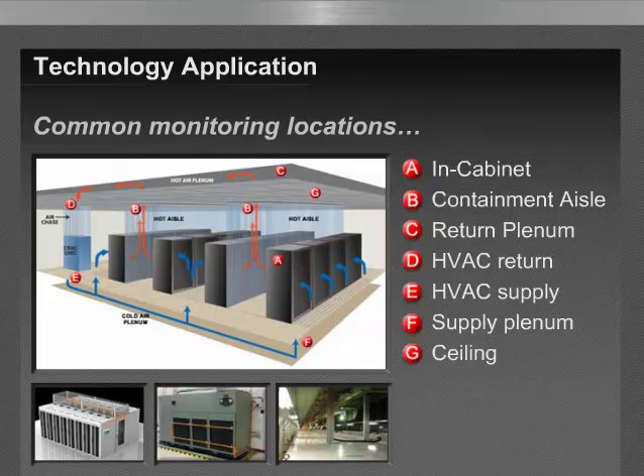And the point we're making here is that the further you get from the source, the greater the compromise. So if we look at the cabinets, for instance, sampling within the cabinets would be ideal. And if you didn't decide to sample within the cabinets, the first place that smoke would migrate to under this hot aisle configuration would be to the return, the ceiling return plenum. And so placement of sampling within the hot aisle at that point presents an opportunity to detect at that location. Now you're making a little bit of a compromise there because you're not able to identify which cabinet, but you're able to identify that one particular cabinet in this particular row had an incident before it got up into the air plenum.